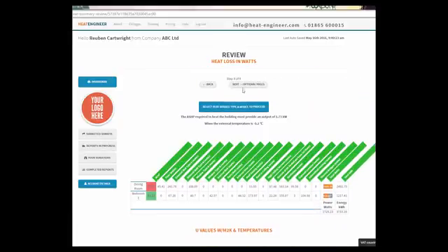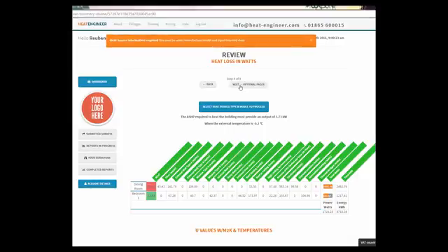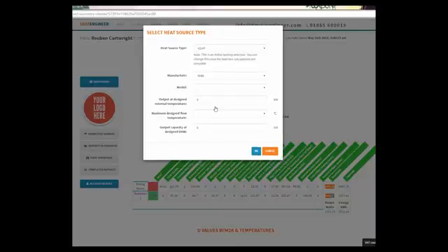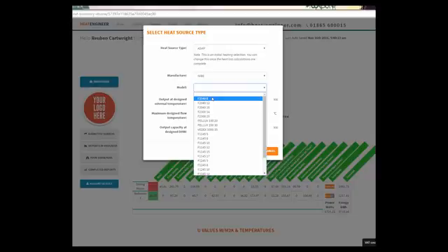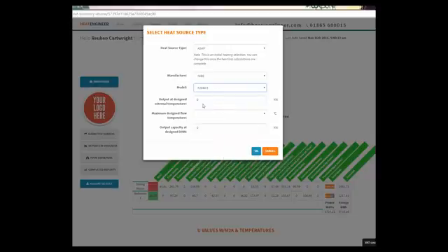So if we go to, I'll just demonstrate. If we go to the optional pages, and it will come up with an indication of what we need to do next. So it says heat source information required. So okay, we select this button here, and the model. So it's an A8, and at this point, it's important to look at manufacturer's data to see what the performance is, what the kilowatt rating is at the external temperature, and at the designed flow temperature to the heating system.